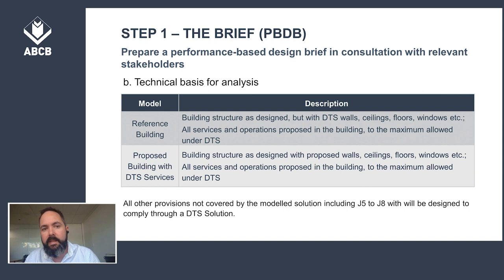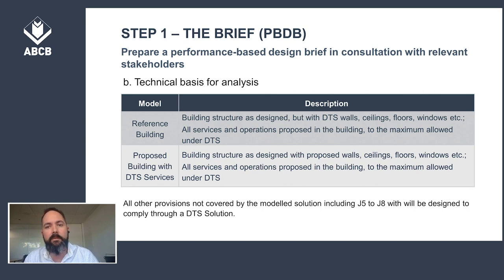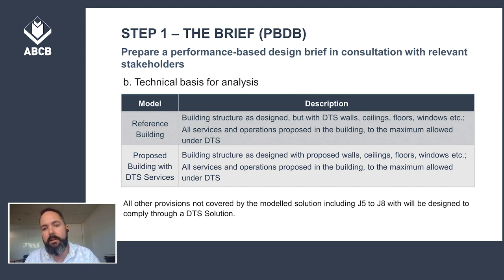We then identify the technical basis for analysis. In this case, the consultant intends to utilise IES-VE energy modelling to calculate the annual load of the building, which has been approved for this purpose being compliant with ASHRAE 140-2007 BESTEST. The modelling software will be used to demonstrate equivalency with Section J building fabric, with added compliance for additional deemed-to-satisfy provisions not covered by the model solution, including general thermal construction compliance with J1.2 and the building sealing to comply with J3. All other provisions not covered by the model solution, including J5 to J8, will be designed compliant with a DTS solution.